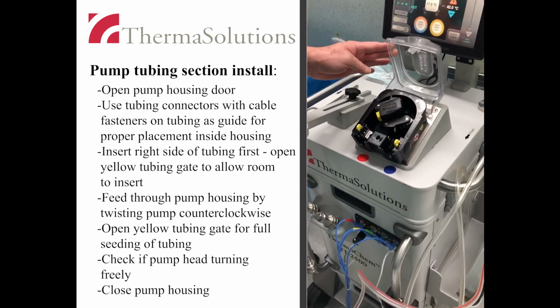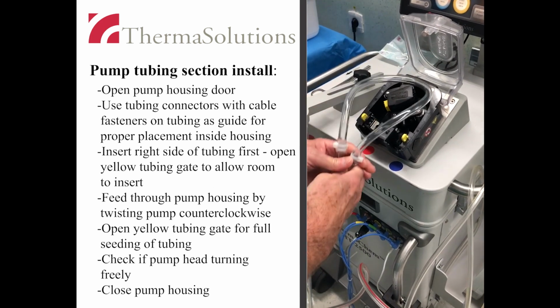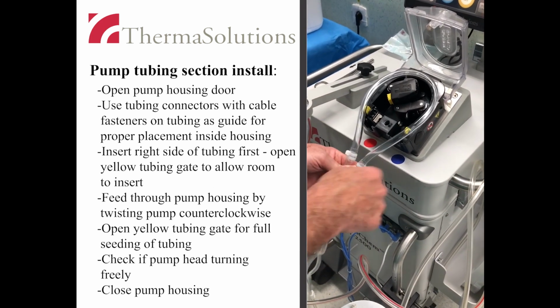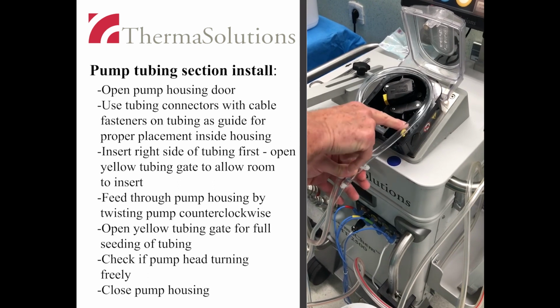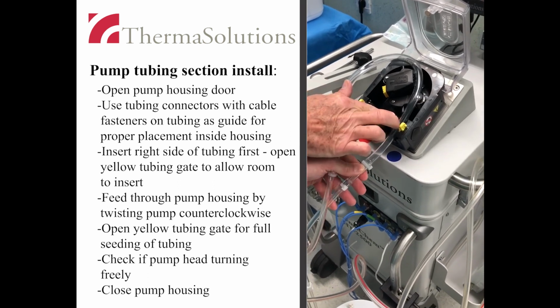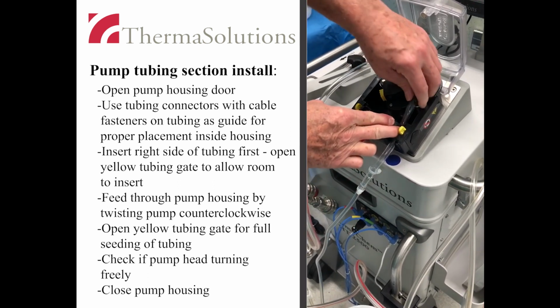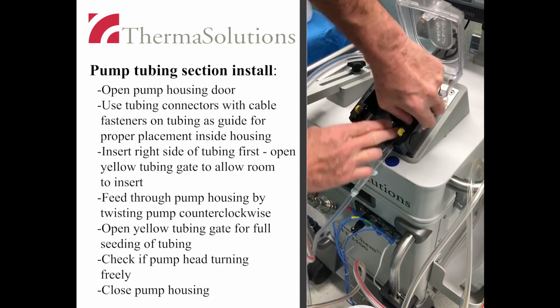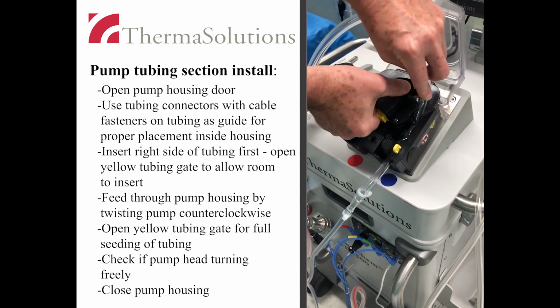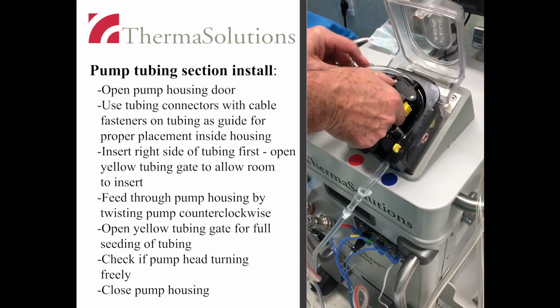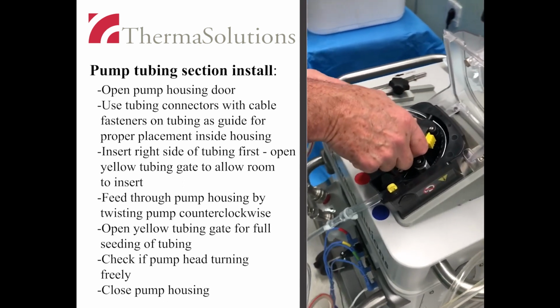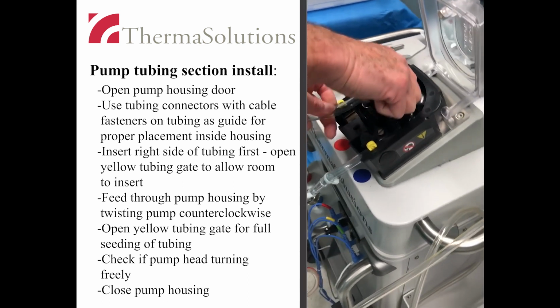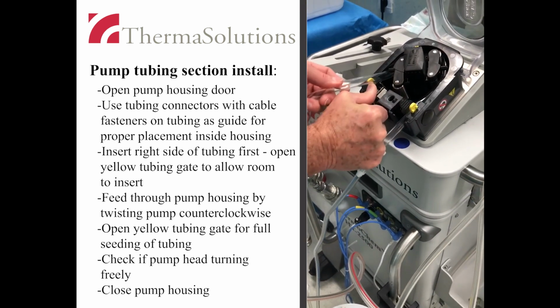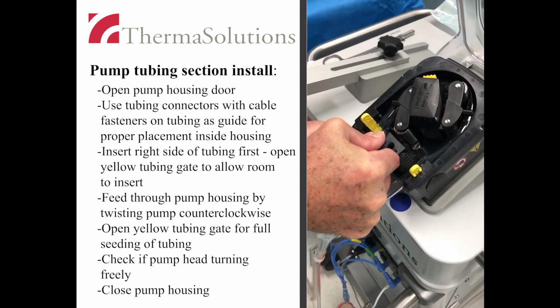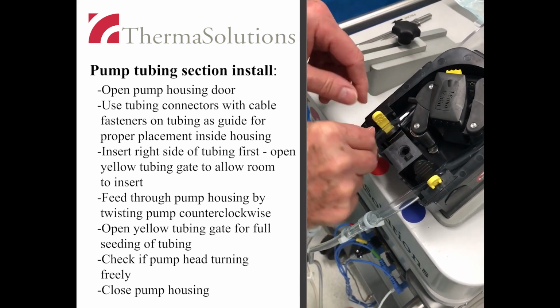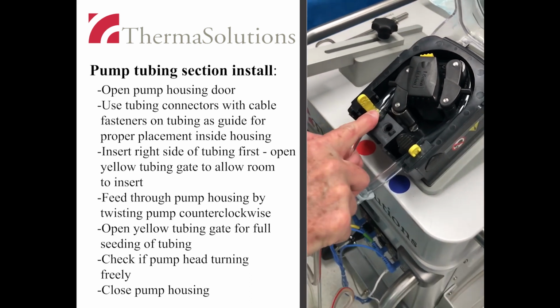Open the pump housing door. Use the tubing connectors with cable fasteners as a guide for proper placement of the tubing within the pump raceway. The connectors and cable fasteners should both be outside the pump housing. Use the colors on the tubing to match the colored dots outside the pump housing as a guide. Insert the right side of the tubing first by opening the yellow tubing gate to allow room to insert the tubing. Feed the tubing through the pump raceway by turning the pump counterclockwise.